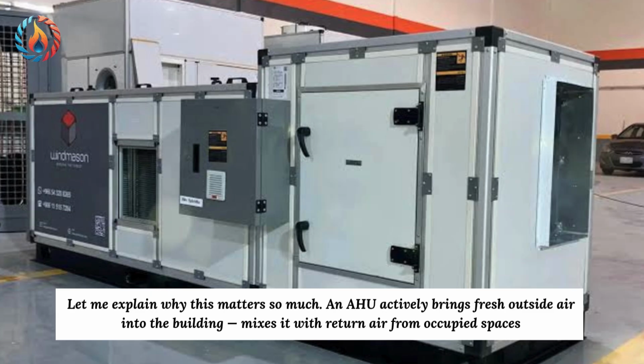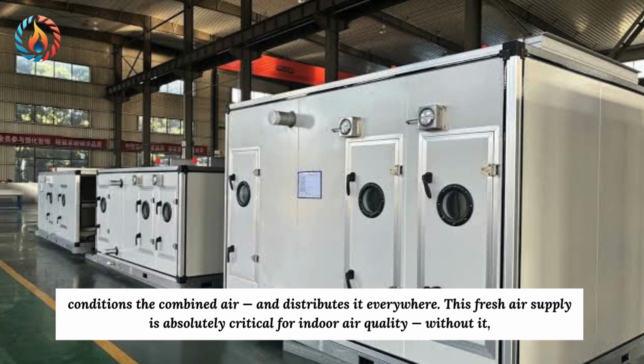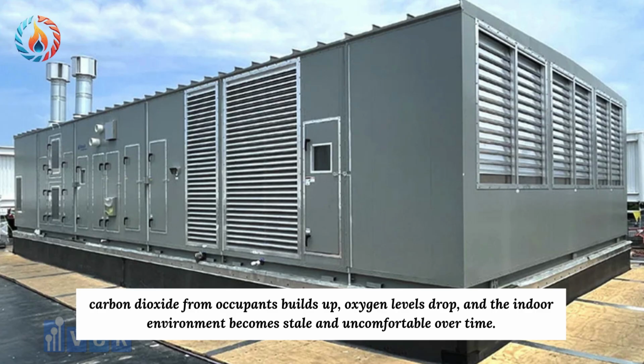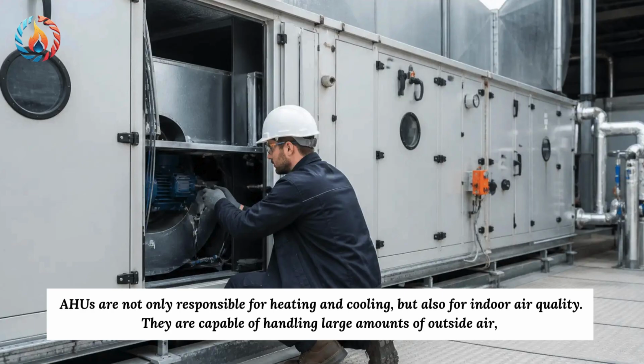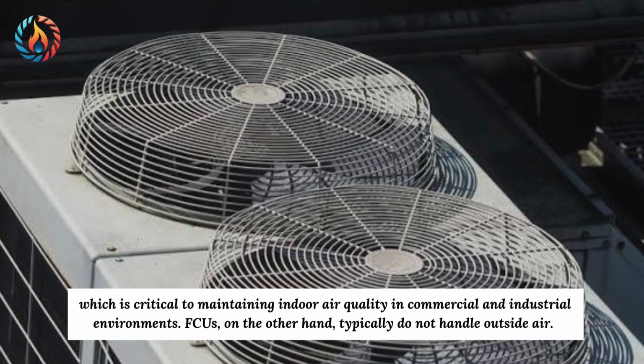An AHU actively brings fresh outside air into the building, mixes it with return air from occupied spaces, conditions the combined air, and distributes it everywhere. This fresh air supply is absolutely critical for indoor air quality. Without it, carbon dioxide from occupants builds up, oxygen levels drop, and the indoor environment becomes stale and uncomfortable over time. AHUs are not only responsible for heating and cooling, but also for indoor air quality. They are capable of handling large amounts of outside air, which is critical to maintaining indoor air quality in commercial and industrial environments.